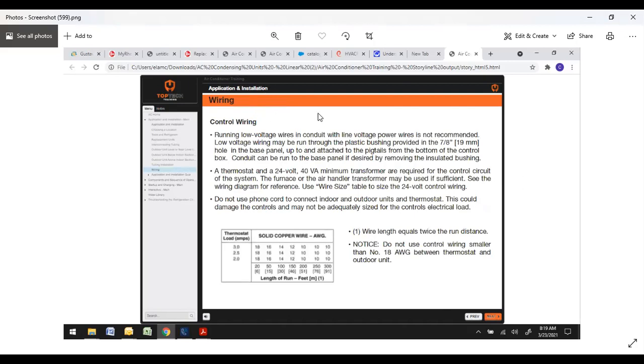As far as your wiring, this is going to be your low voltage control wiring. They do recommend not to run your low voltage wire in the same conduit with your line voltage. Low voltage wire may be run through the plastic bushing provided in the base panel and attached to the pigtails. A standard thermostat and a 24 volt, 40 VA minimum transformer are required for the control circuit of the system. The furnace or air handler transformer may be used if it's sufficient, and most new ones should be a minimum 40 VA.